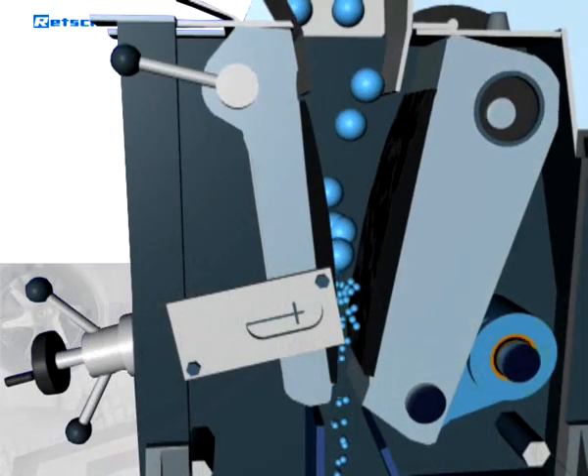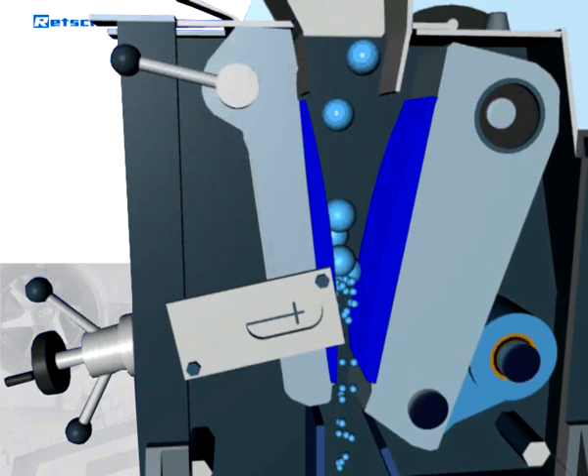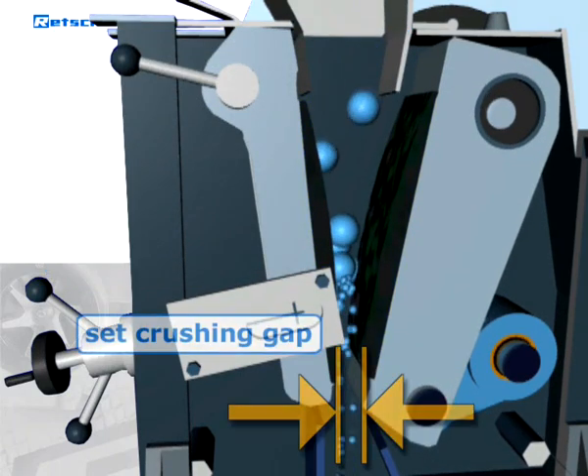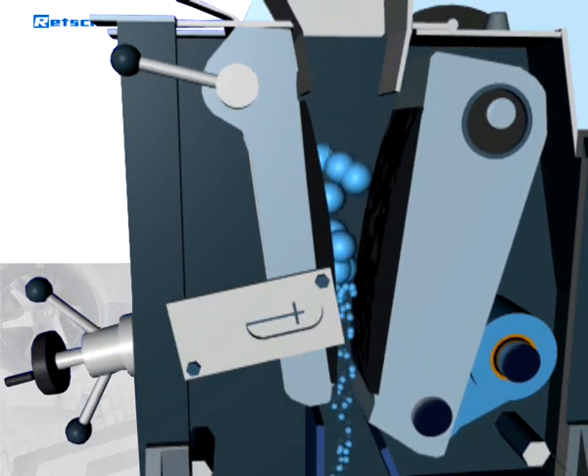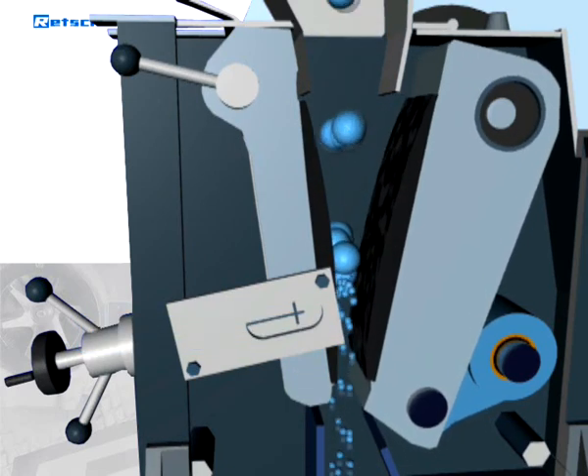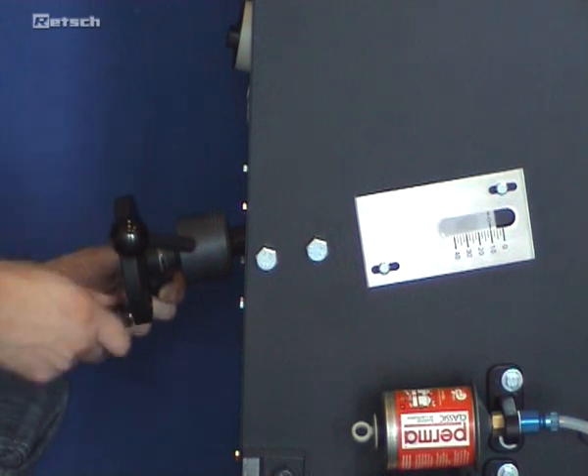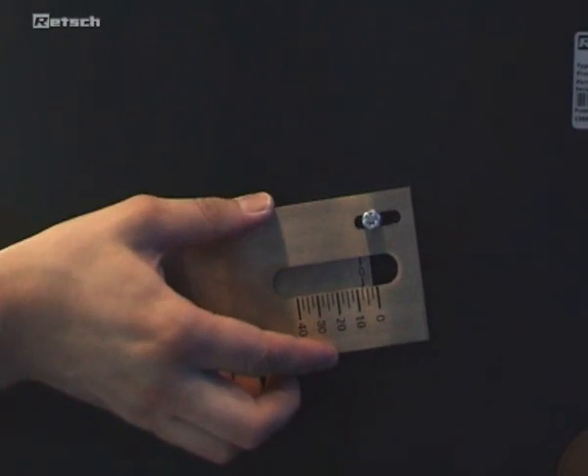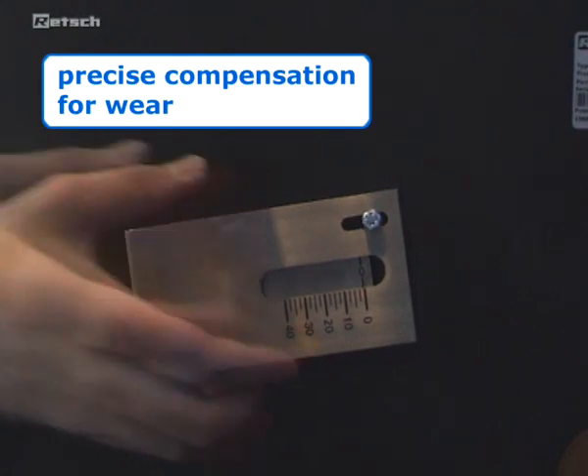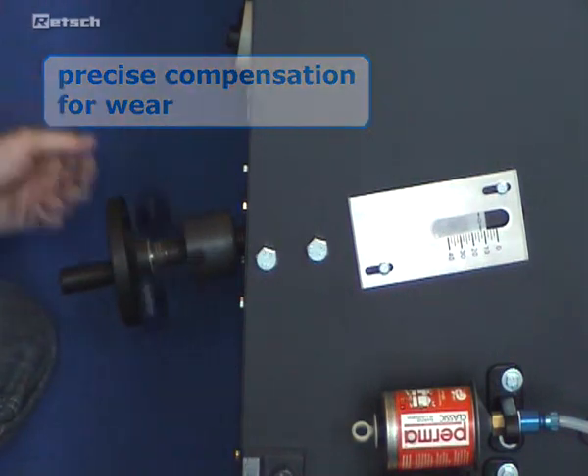Depending on the material and throughput, even high-quality breaking jaws will eventually show signs of wear, meaning the set crushing gap will increase over time. In order to obtain reproducible crushing results, this wear must be compensated. With traditional jaw crushers, whose gap width can only be set in fixed steps, accurate compensation is not possible. Retsch jaw crushers can be continuously adjusted, so the wear of breaking jaws can be compensated precisely.